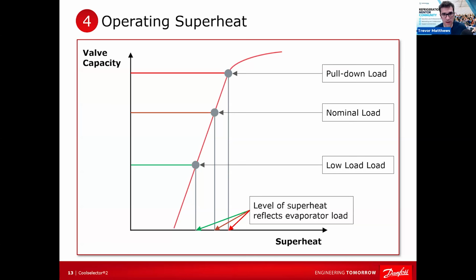And then I'm like, let me go try this on a TX valve. So then I went and tried to drop this load. And then all of a sudden you would see the valve just hunting because I had a bunch of monitors on it. Then I increased the superheat on the valve and it started to run perfectly.